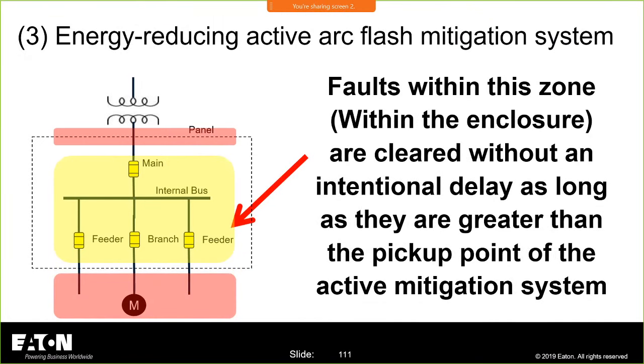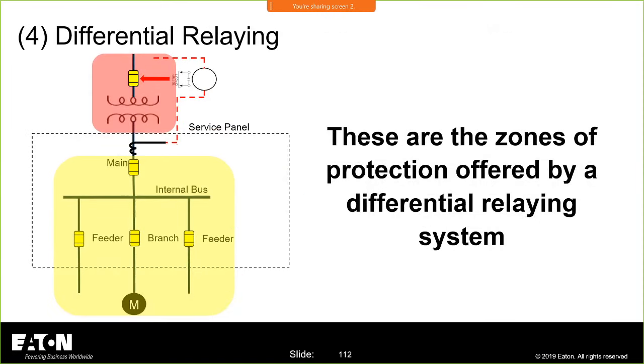This is, again, an energy reduction, the active energy reduction system. I'll have a video of that a little bit later. It, again, has a zone of protection. So if you're working down here, you don't get protection because it's only looking up there. This is not differential relaying. I keep telling myself I need to fix this.